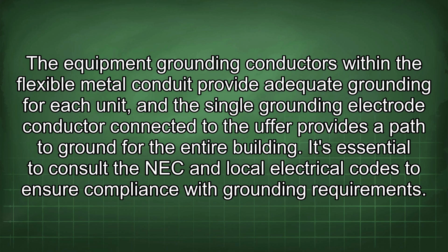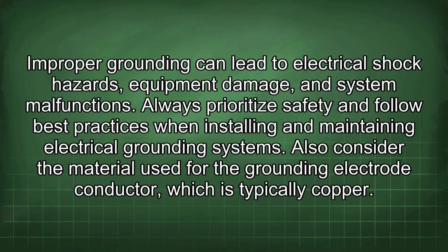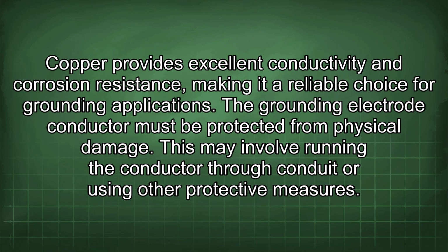It's essential to consult the NEC and local electrical codes to ensure compliance with grounding requirements. Improper grounding can lead to electrical shock hazards, equipment damage, and system malfunctions. Always prioritize safety and follow best practices when installing and maintaining electrical grounding systems. Also consider the material used for the grounding electrode conductor, which is typically copper. Copper provides excellent conductivity and corrosion resistance, making it a reliable choice for grounding applications.